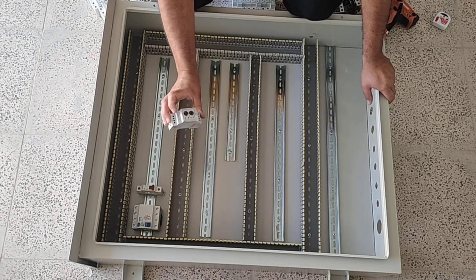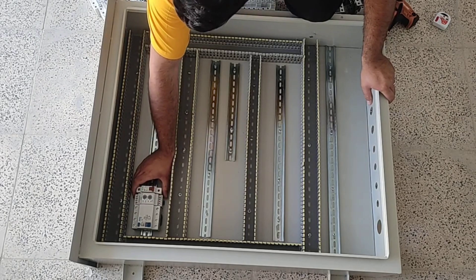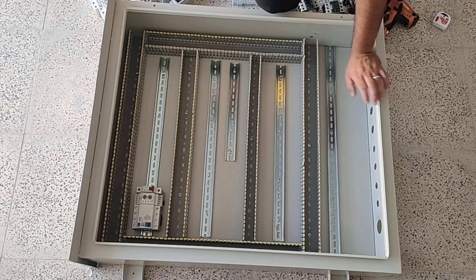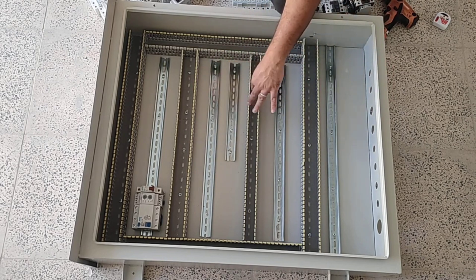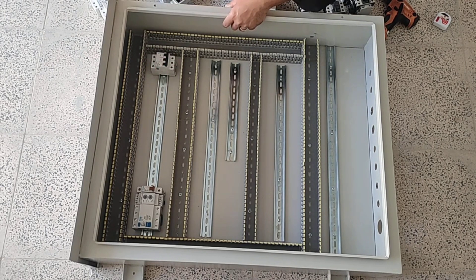Next to the RCCB switch we use a phase controller relay that controls the voltage of the phases and cuts off the command circuit in case of an error. This switchboard contains four contactor outputs, so we need contactors. For each three-phase contactor output we put a miniature switch to protect the corresponding circuit from short circuit.